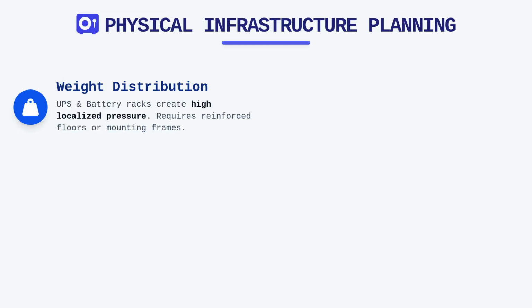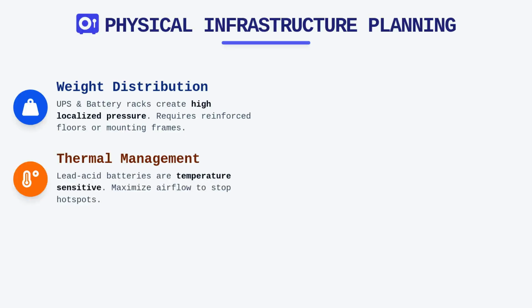Designers must also be conscious of the physical infrastructure surrounding these power systems, particularly regarding weight distribution and thermal requirements. Large UPS cabinets and battery racks can exert high localized pressure on raised floor systems, requiring reinforced structural supports or specialized mounting frames. Ventilation is not merely a matter of comfort, it is a necessity for heat dissipation, as lead-acid batteries are highly sensitive to ambient temperature fluctuations that can shorten their design life significantly.